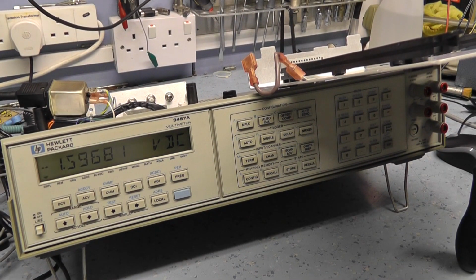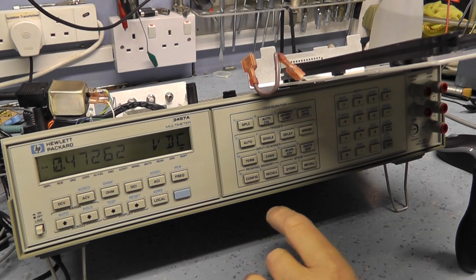Okay, let's read out what it says. It says, run the reconnect and turn the power on. Run the AC Auto Cal routine. Press Auto Cal configuration key. Enter the number 2. So Auto Cal number 2. What else does it say? I press enter. And then it says, what does it say there? Just trying to make sure I'm getting this right. So enter diagnostic routine number 8. Press the blue shift key and the auto 0 key.